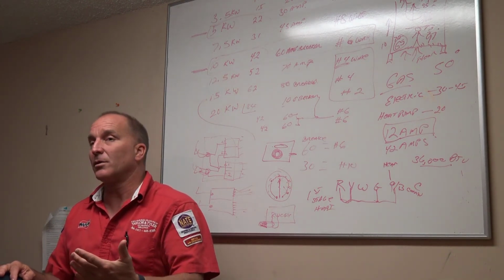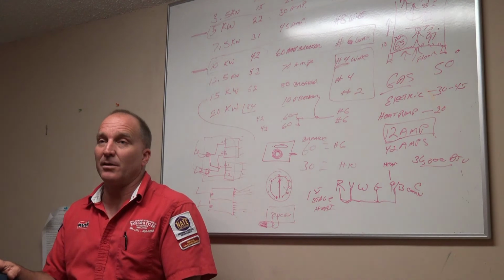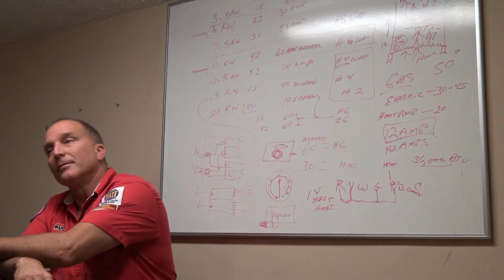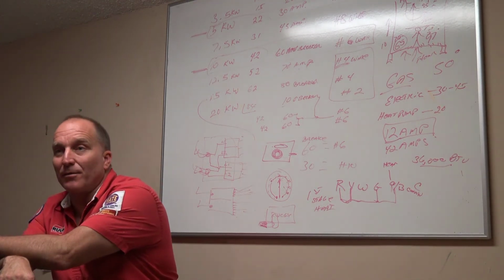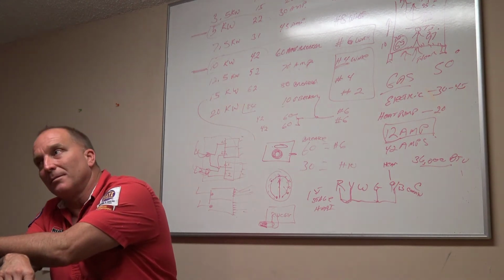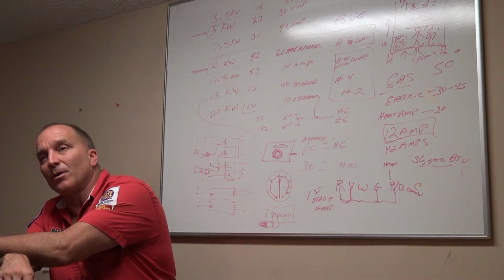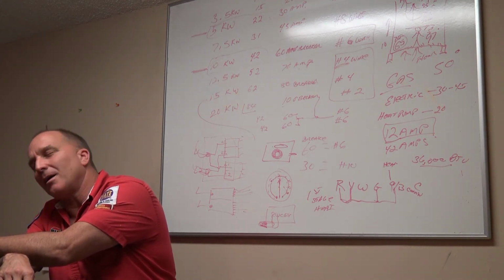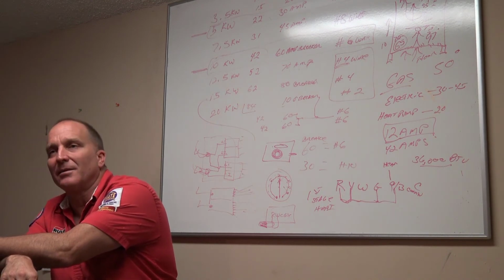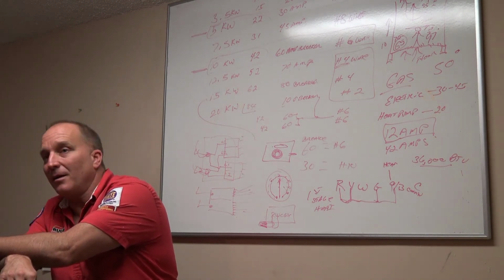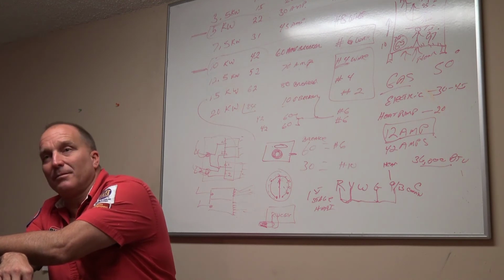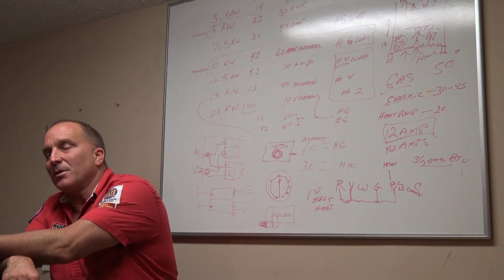You need to add refrigerant to the system, but you know what? Your system's 15 years old, and I'll sell you a new unit. So now I made $10,000 off of go and check my pressures because I didn't shortcut myself. I didn't shortcut the customer. I can't tell you how many times that has happened to me, guys. Because I get tired. I don't want to do it, you know? And that's what's going to happen to you.